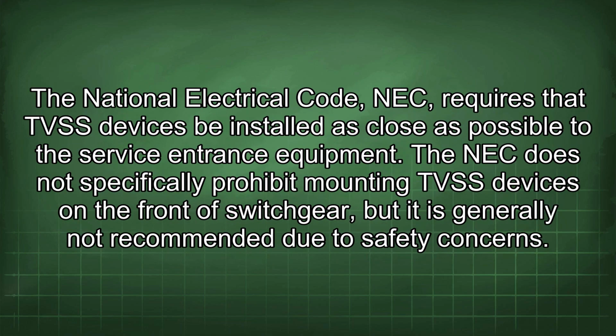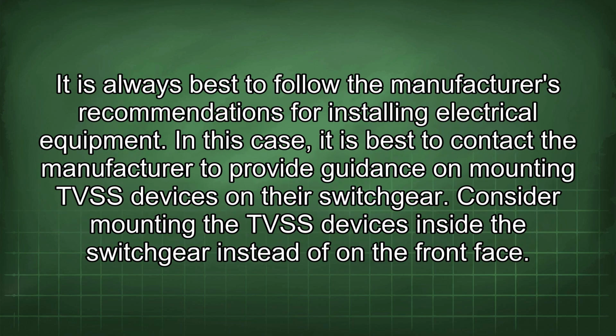The National Electrical Code (NEC) requires that TVSS devices be installed as close as possible to the service entrance equipment. The NEC does not specifically prohibit mounting TVSS devices on the front of switchgear, but it is generally not recommended due to safety concerns. It is always best to follow the manufacturer's recommendations for installing electrical equipment. In this case, it is best to contact the manufacturer to provide guidance on mounting TVSS devices on their switchgear.